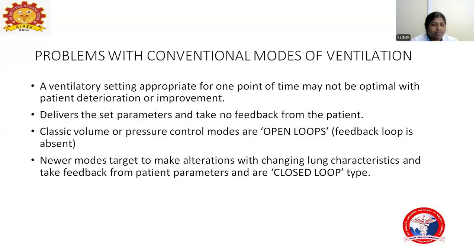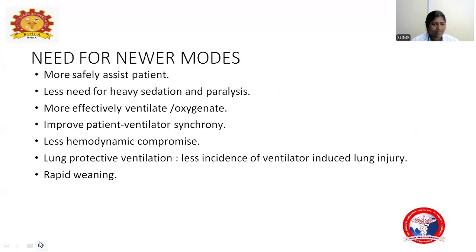So the conventional mode of ventilation will deliver the set parameters and will not take any feedback from the patient. The classical volume or pressure control modes are open loop, which means the feedback loop is absent. But newer modes target to make alterations with changing lung characteristics and take feedback from the patient, and they are called closed loop type.